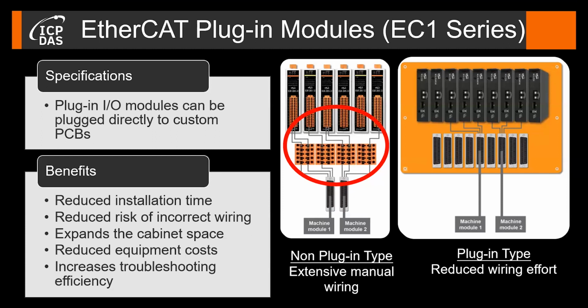The figure on the left shows the conventional point-to-point wiring process needed for connecting remote EtherCAT I/O modules. Each I/O channel, each I/O point has to be wired one by one, individually, to an external device, such as a switch, valve, sensor, or actuator. So external manual wiring of single wires is time-consuming and increases the risk of incorrect wiring.